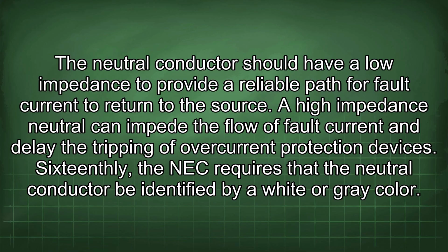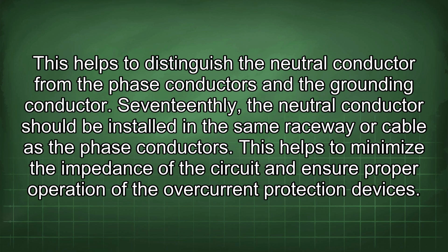16thly, the NEC requires that the neutral conductor be identified by a white or grey color. This helps to distinguish the neutral conductor from the phase conductors and the grounding conductor. 17thly, the neutral conductor should be installed in the same raceway or cable as the phase conductors. This helps to minimize the impedance of the circuit and ensure proper operation of the overcurrent protection devices.